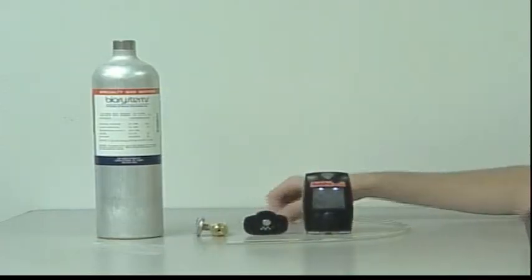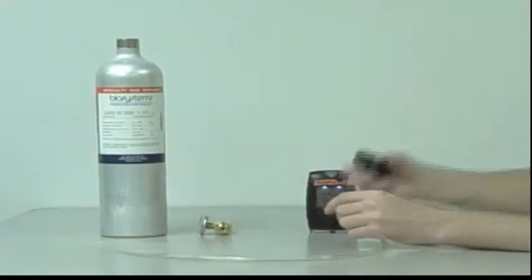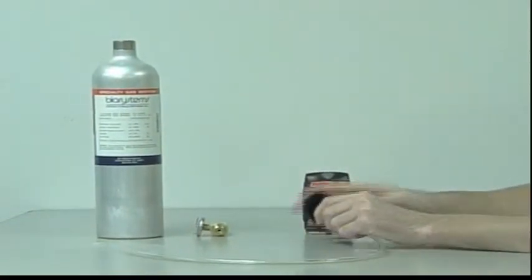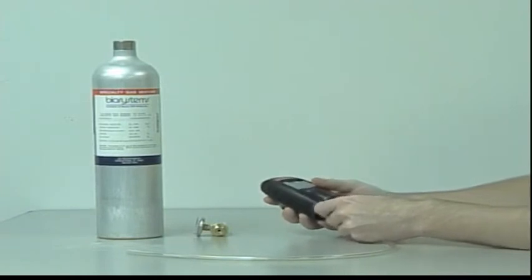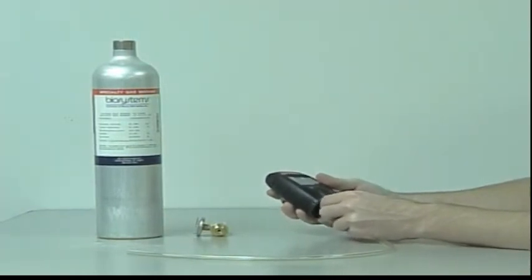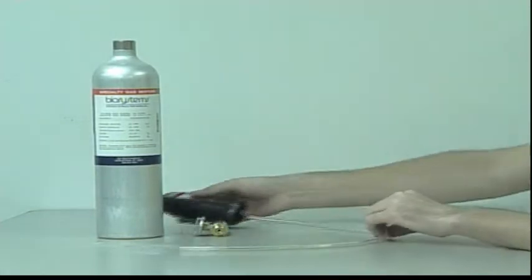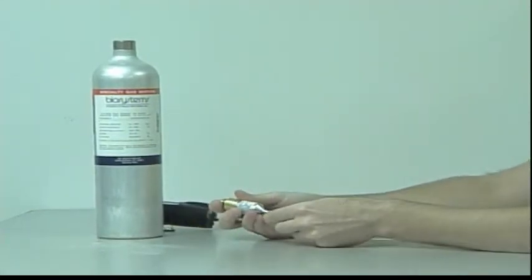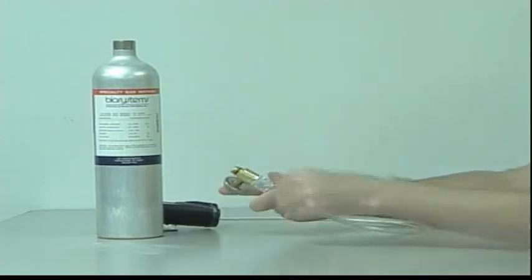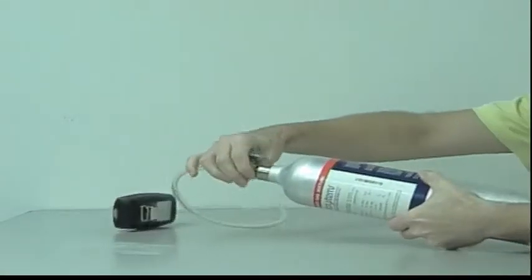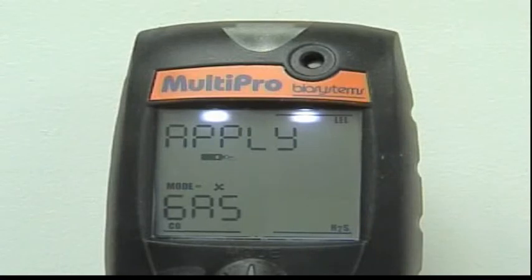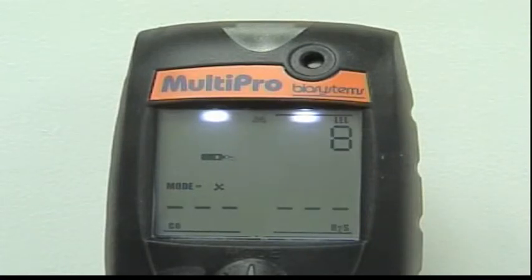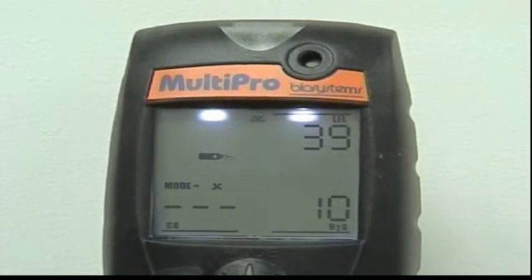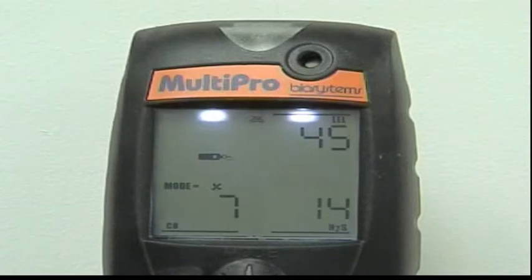Attach the calibration gas cylinder, regulator, and calibration adapter with a short section of tubing to the MultiPro. Make sure that the cylinder threads and seating surfaces are clean and dry when attaching the regulator to the gas cylinder. Once the instrument recognizes the calibration gas, the current gas readings will be shown with the sensor types. The calibration is fully automatic from this point on. Upon successful calibration of a sensor, the MultiPro will beep and show the adjusted reading for the calibrated sensor, and then move on to the next sensor.